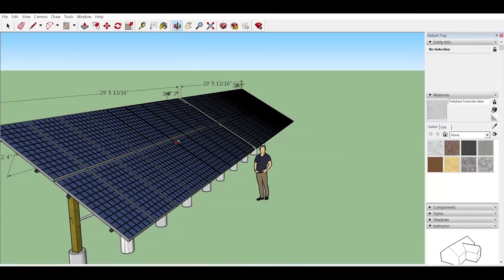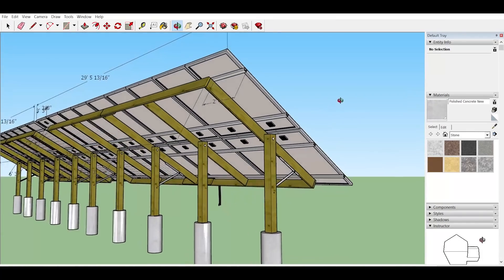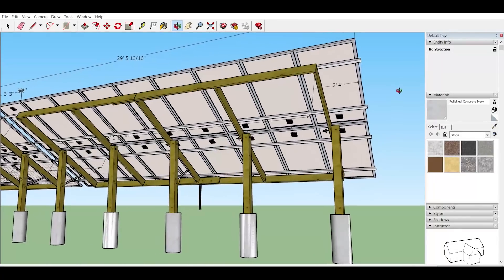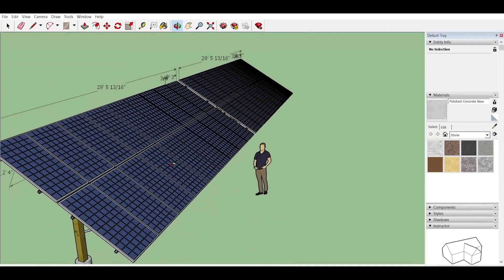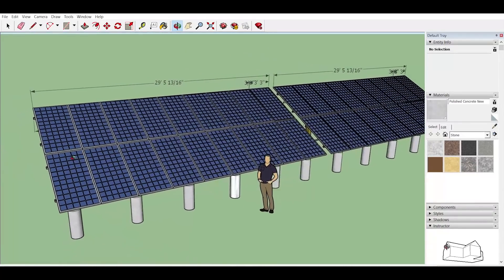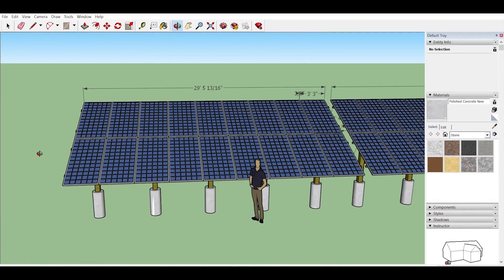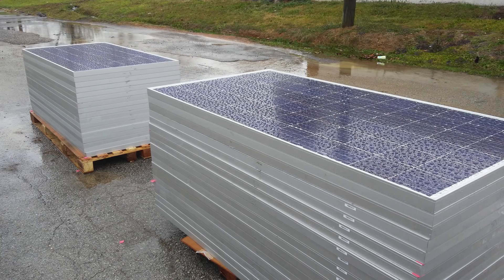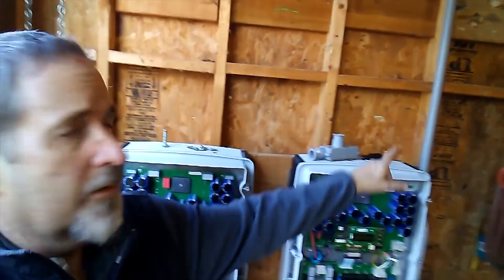In this video I'm going to show you how we built a 10,000 watt solar farm. I used SketchUp to design the system to be a ground mount and it's tiltable to maximize the output for summertime or winter. Since we used low-cost materials and waited to find a good price on some surplus solar panels that were brand new, we expect about a four-year return on the investment. We ended up with 315 watt four bus bar solar panels made by JA Solar, and we're using the Sunny Boy SMA 5000 US solar string inverters.